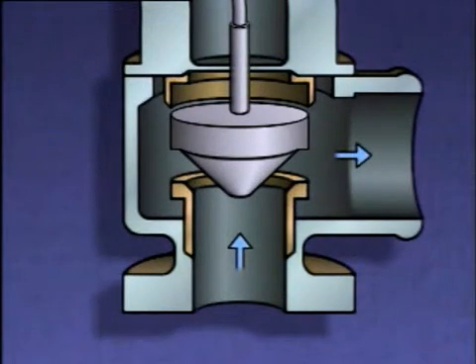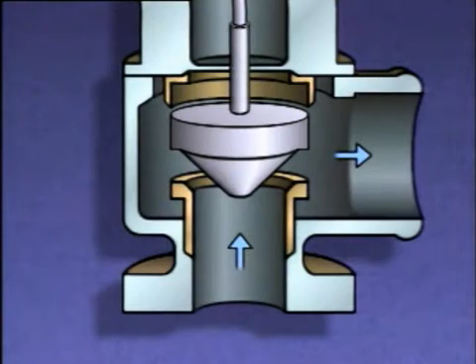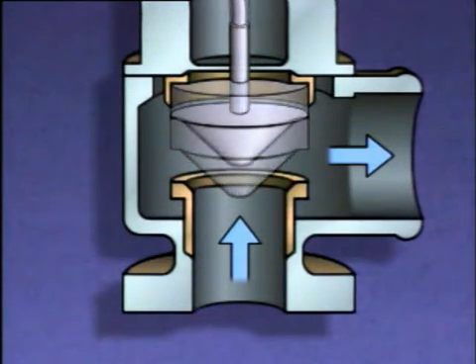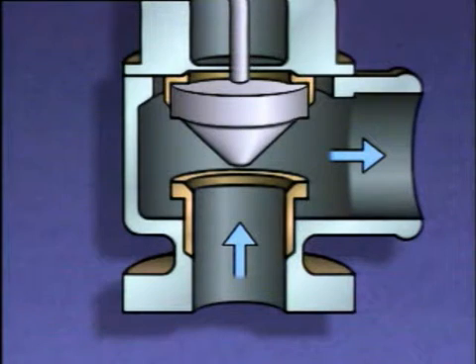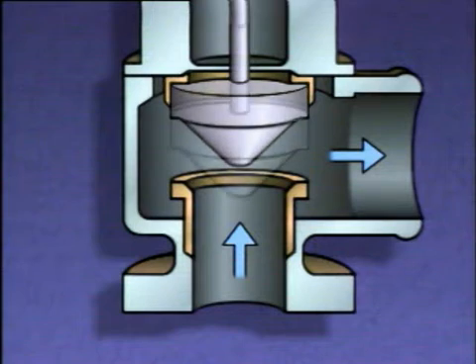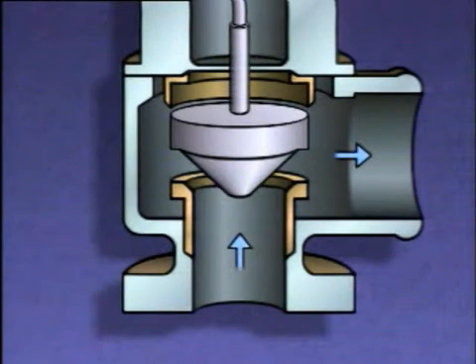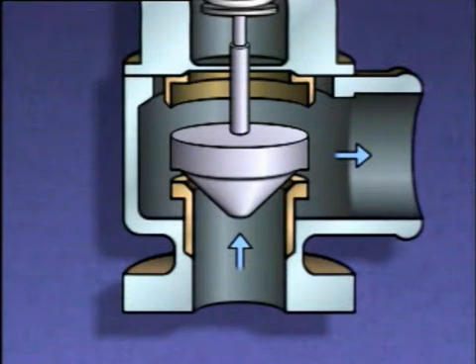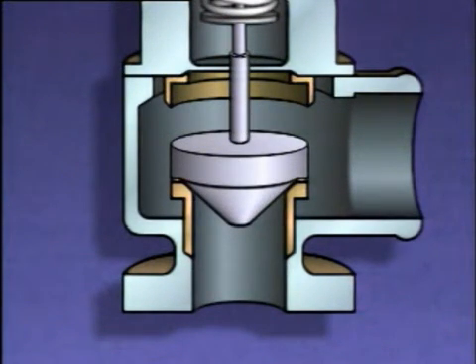This allows a large volume of liquid or gas to escape rapidly. If pressure in the system keeps getting higher, the pressure acting on the bottom of the disc will also increase and cause the disc to lift even higher. Once the excess pressure in the system has been relieved, the system pressure will begin to drop. As pressure goes down, the force acting on the bottom of the disc also decreases. Eventually, the force exerted by the spring takes over and pushes the disc down. However, when the system pressure gets down to 200 PSI, the valve still doesn't close because the lip of the disc is still exposed to the pressure of the escaping liquid or gas. The valve won't close until system pressure drops below the pressure needed to pop the safety valve open.